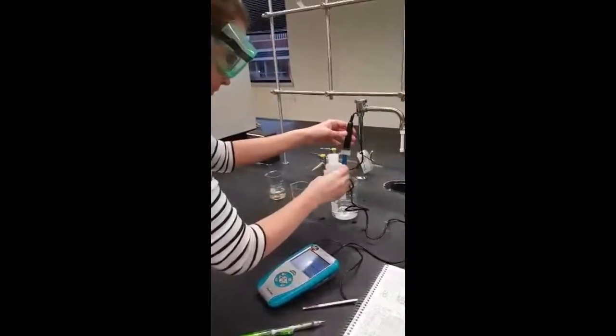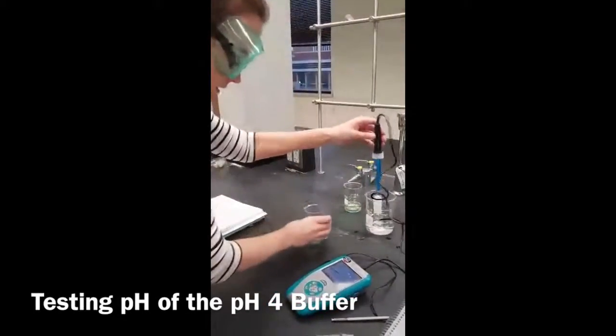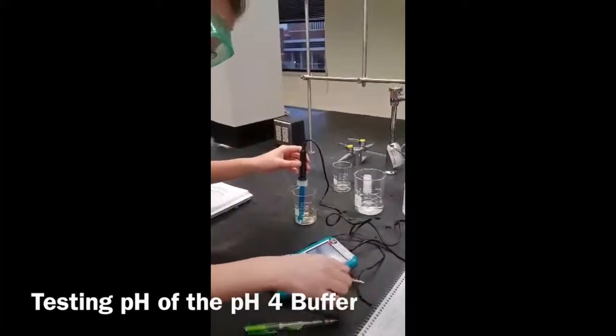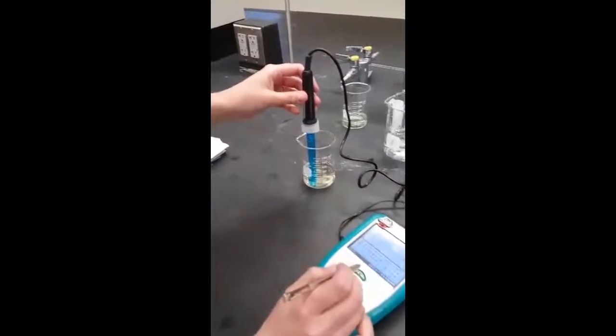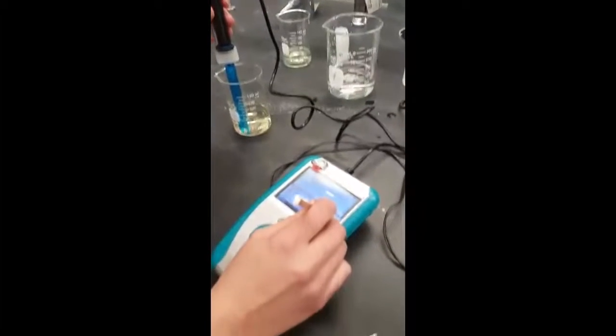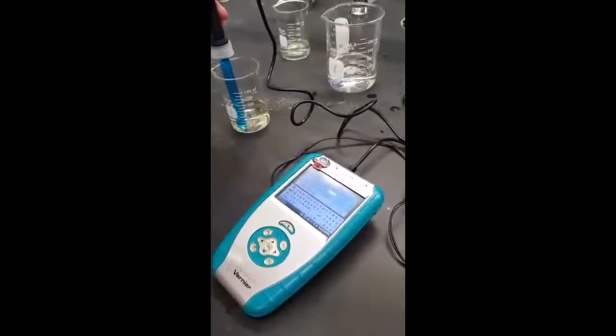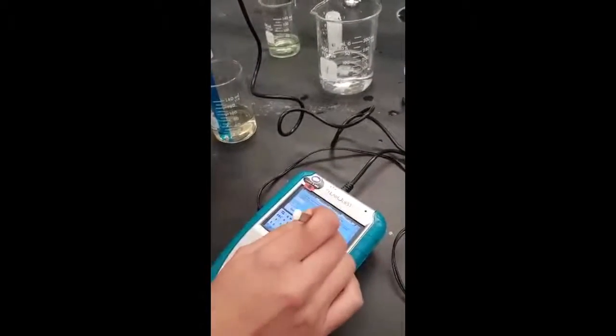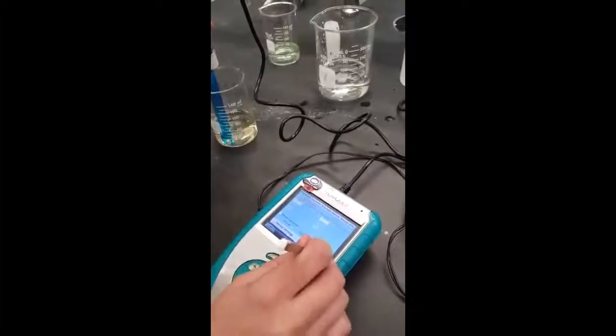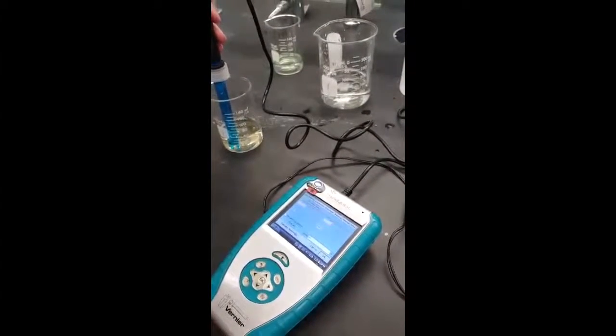I will wait for the voltage to stabilize, then adjust the pH reading on the meter to 7.00 and then press Keep. I am now removing the electrode and rinsing with distilled water over the waste beaker, then placing the electrode in the pH 4 buffer solution to ensure the meter is ready to use.